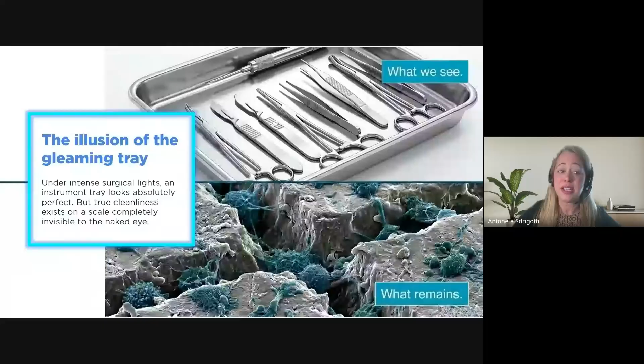Sterilization failure rarely starts in the sterilizer. It starts in the washer. Cleaning is not a visual process. It is a measurable biochemical process. If organic residues remain, sterilization becomes a gamble. So this is the illusion of the gleaming tray: what we see, and what really remains. Under intense surgical lights, an instrument tray looks absolutely perfect, but true cleanliness exists on a scale completely invisible to the naked eye.